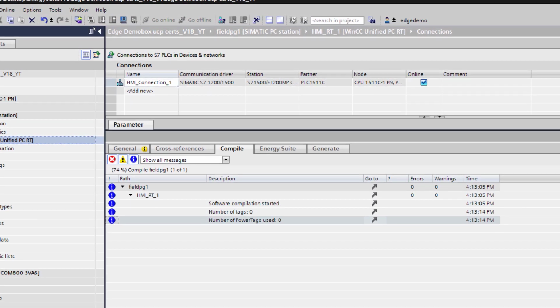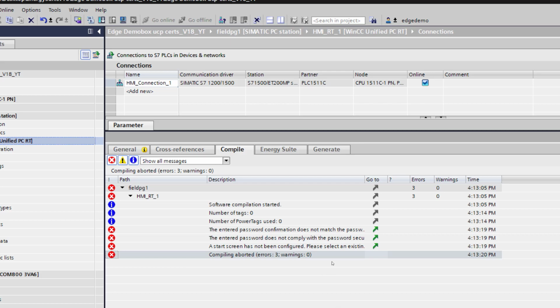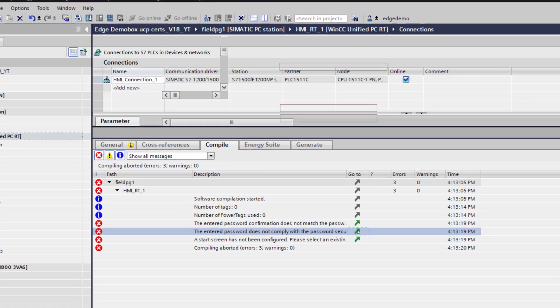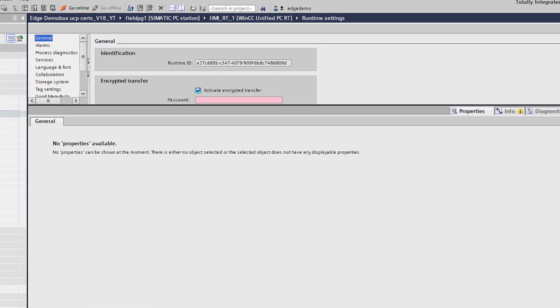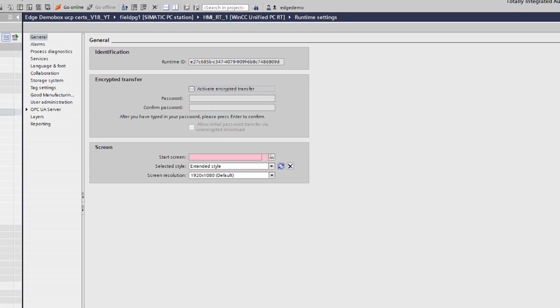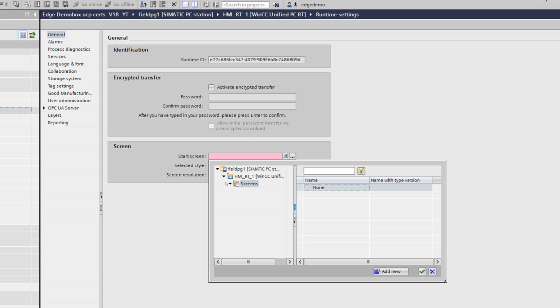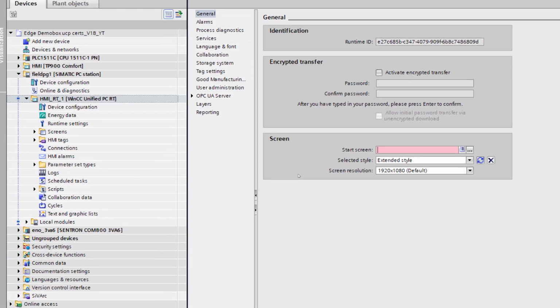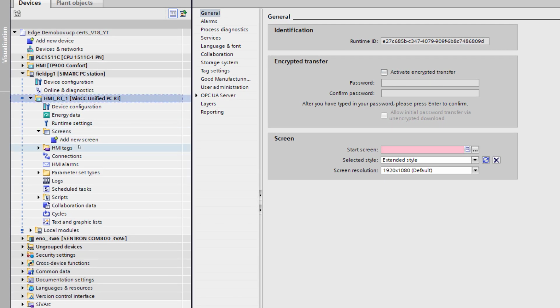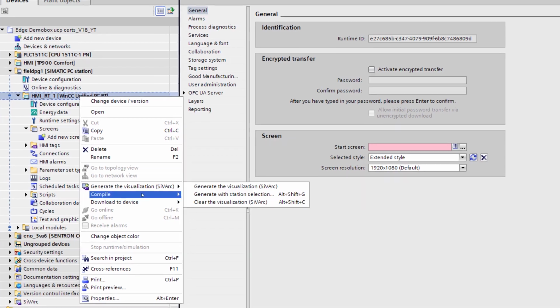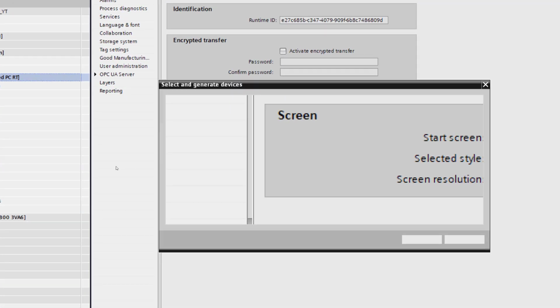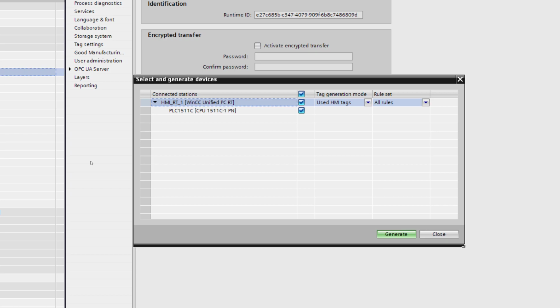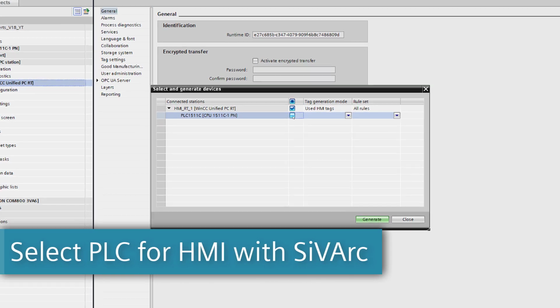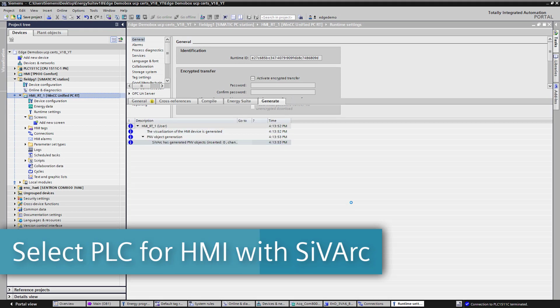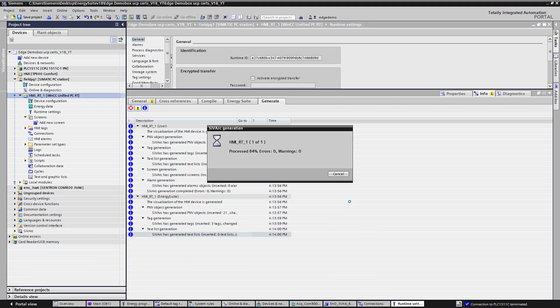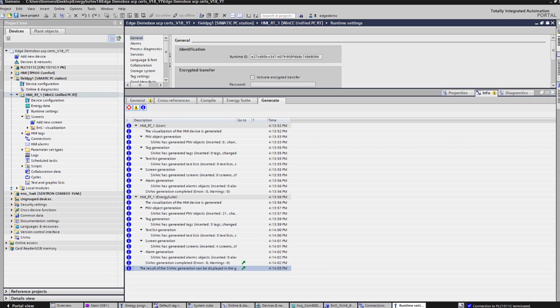So there are two errors that resolve here. One is the effect of an encrypted transfer password configuration. Here you'll see me deactivate it for the demonstration here. And then also that we don't have a declared start screen. That's okay, we're going to fix that now because we'll use SiVArc to auto-generate the HMI. What we've got to do is select the PLC that we want to connect to with SiVArc, and that will link us with the HMI. Processed with no errors. And now we can go ahead and link the start screen.